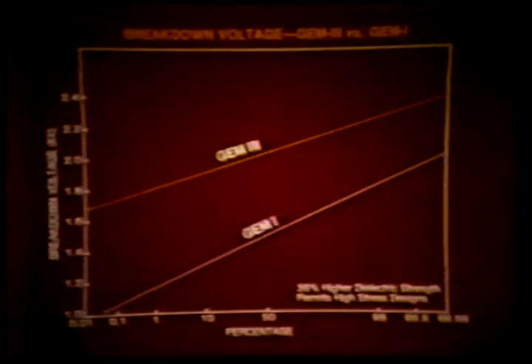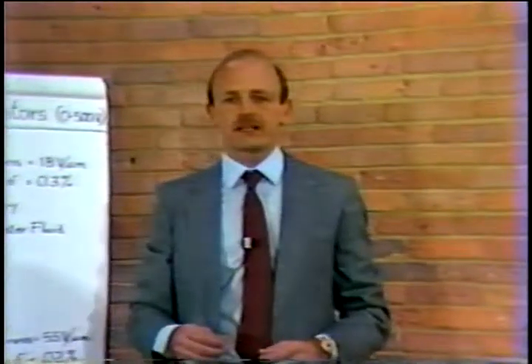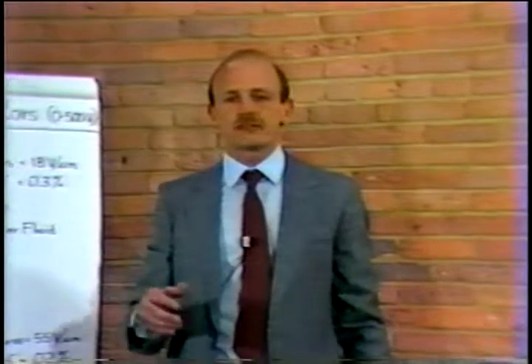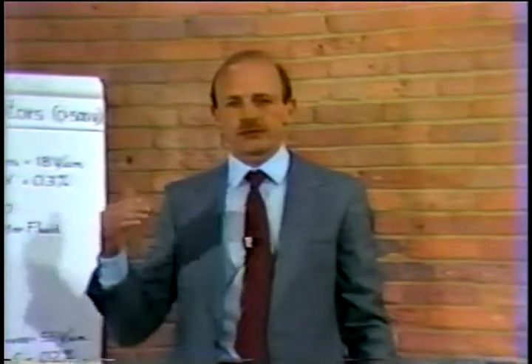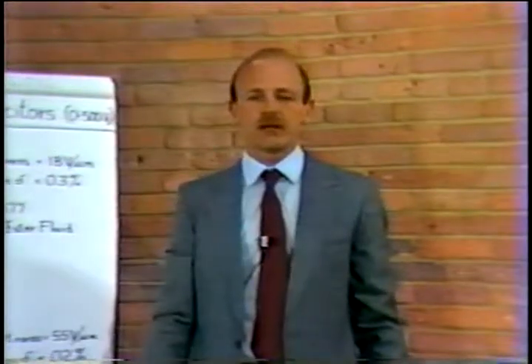Here we see a comparison of the effect of the high resistivity Gem 3 electrodes compared with the lower resistivity Gem 1 electrodes. The breakdown voltage is plotted as a function of the percent survival. We see that the Gem 3 electrodes provide approximately 36% higher dielectric strength than the Gem 1 electrodes. I believe this is a classic example of how understanding failure mechanisms can lead to improvements in capacitor technology. Through these improvements, we're able to increase the voltage from 300 volts up to 500 volts in a metallized construction.